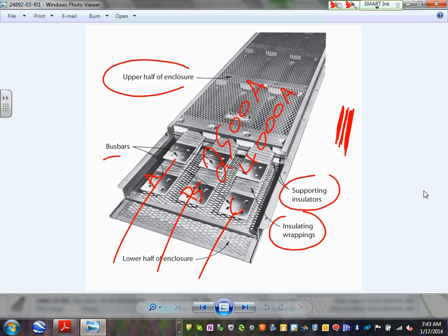Well, they don't. There's a bolt that goes right through here, but inside the bolt there is insulation. That's where they put the three phases together, and there's a hole designed with an insulation. They put a bolt right through them and torque them to make sure they stay within a limit, within certain distances. There's a whole lot of techniques for putting them together, and you're going to see it.